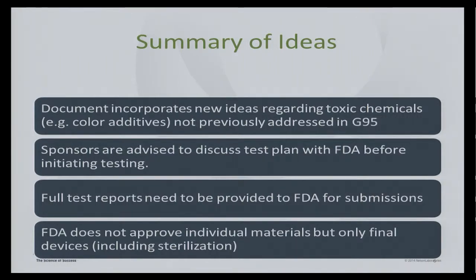This is also something that you'll see throughout, like a thread throughout the whole document, which is the FDA does not approve single materials. We have a lot of devices that are made out of FDA or biocompatible biomaterials. And a lot of people will try to say, look, I'm using polypropylene, I'm using PEEK, they all have medical grade certifications, I don't need to do any biocomp. The FDA does not approve just materials because there's processing that goes into making the device and you're sterilizing it, which can have an impact on biocompatibility. So when you're looking at justifying out of a test, you can't just look at materials, but you also have to look at what you're doing to those materials as part of your justification.